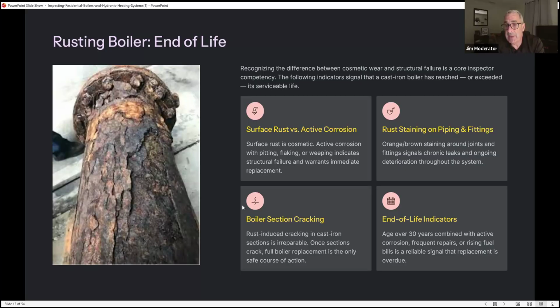Rust staining on pipes and fittings: orange-brown staining around joints and fittings signals chronic leaks and ongoing deterioration throughout the system. Boiler section cracking. Rust-induced cracking in cast iron sections is irreparable. Once sections crack, full boiler replacement is the only safe course of action. And end-of-life indicators. Age over 30 years combined with active corrosion, frequent repairs, or rising fuel bills is a reliable signal that replacement is overdue.